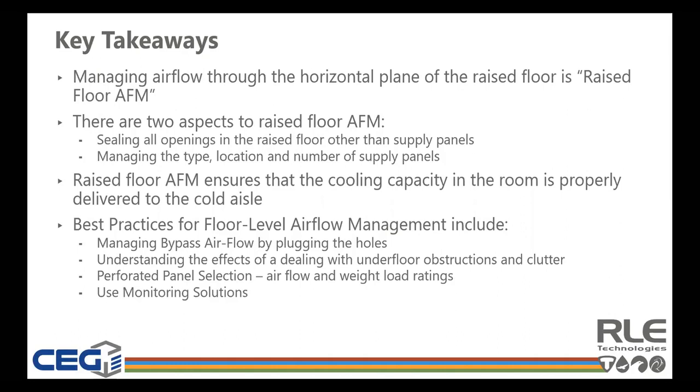Understanding the negative effects of underfloor obstructions and clutter, and the best practice to deal with that and manage it. I mean, you do virtualization or put applications in the cloud, and you hear a lot of people talk about stranded capacity in the racks. These are servers or other devices that are on, consuming power and not doing anything. And you pull those out, right? And you get rid of them, and you have available capacity you just reclaimed. But there's not a lot of talk about the same thing going on under the floor. So if you can do it, I'd get started. It's going to do nothing but help you longer term.